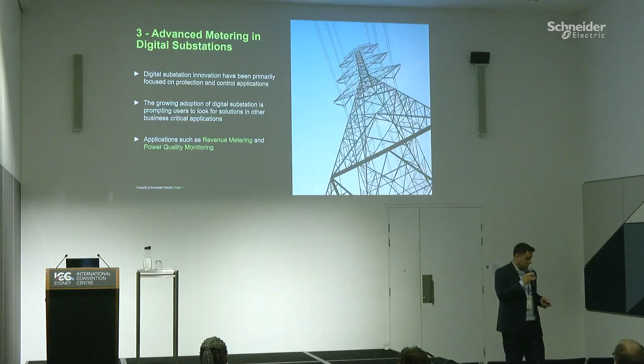I chose 4 different challenges here, but there's more than 4. The first one is around calibration and traceability. As I mentioned before, a key characteristic of a power quality and revenue meter is accuracy. That accuracy needs to be verified. Those meters need to be calibrated and verified often, every 3 years, every 5 years, depending on where you are in the world.